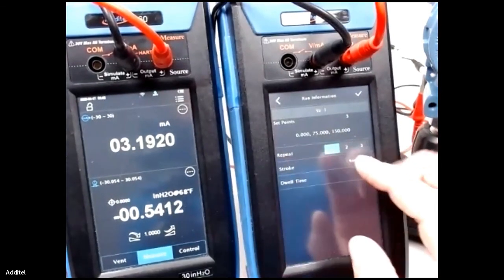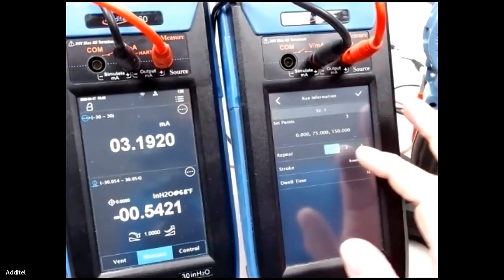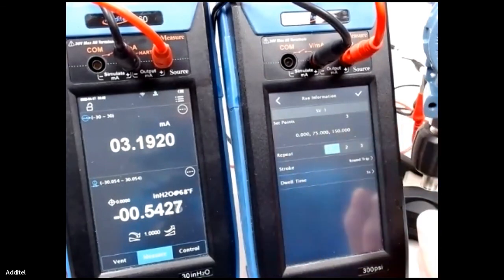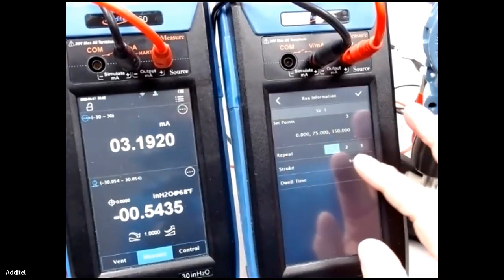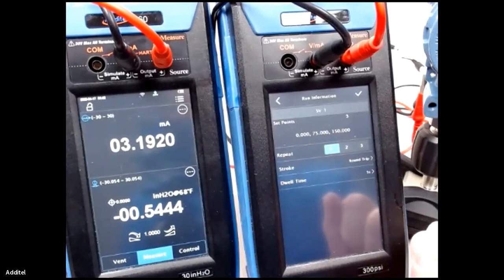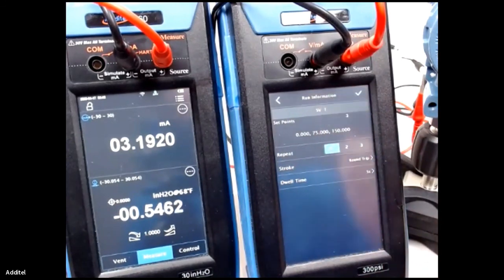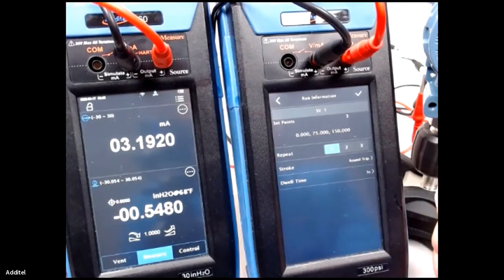This next feature allows you to do it however many times, 1, 2, or 3 times. We're just going to do it once, and we're going to do a round trip. The reason we're doing a round trip is it's going to show us the hysteresis value of the sensor as it goes up and down. And we're going to wait 5 seconds each time it becomes stable.